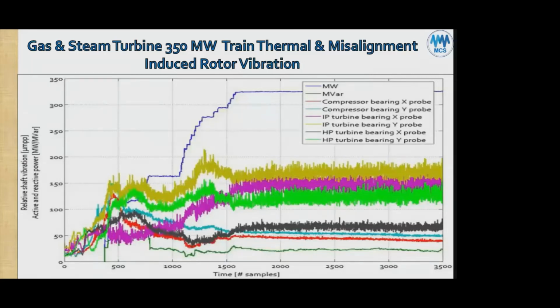Another example, here we have a gas and steam turbine on one train, 350 megawatt output. It's a cogeneration unit. And this is the time versus vibration amplitude on the main bearings of the machine, and trended with power, with megawatt. The blue on the top is the megawatt power. And the other MVar is the reactive power. So we just stick to the active power, which is the megawatt. So you can see at the top, they're almost reaching rated power of 330 megawatt. And as they started from 0 time, we have the vibrations coming up gradually.